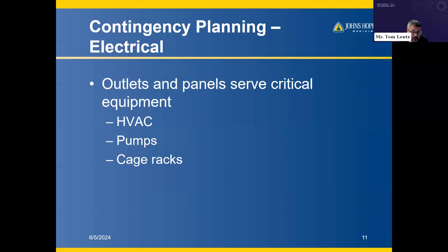We learned this during Superstorm Sandy up in New York, where the generators were great and they had plenty of fuel, but if your fuel pumps can't get fuel to where it needs to go, then your generators can't run. And the impact on ventilation within the cage racks is also vitally important.